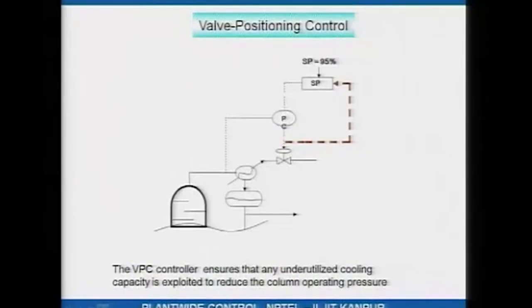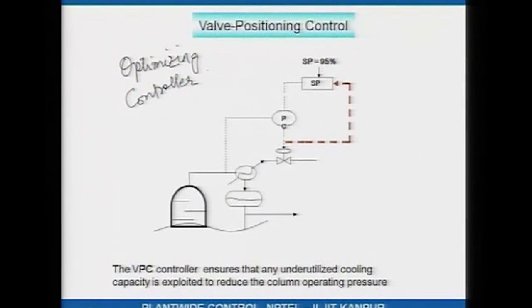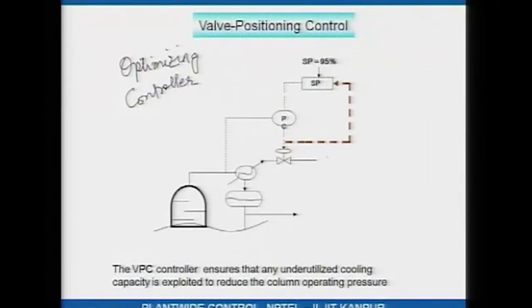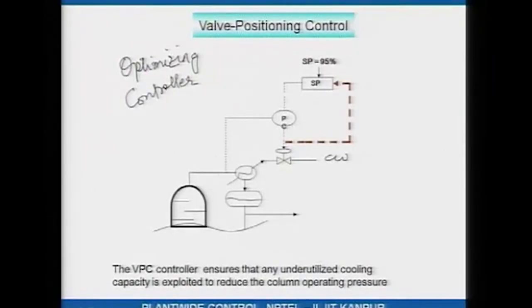Another very useful control structure is called the valve positioning controller, sometimes also referred to as an optimizing controller or optimizing control. What it does is best explained using an example. Ordinarily in distillation columns, the hot vapour is condensed in the condenser using cooling water. If the pressure of the column is increasing, that means more vapour needs to be condensed, so you increase the cooling water flow, condensation rate goes up, and the pressure gets back down. This is how ordinarily pressure is controlled in most industrial columns.